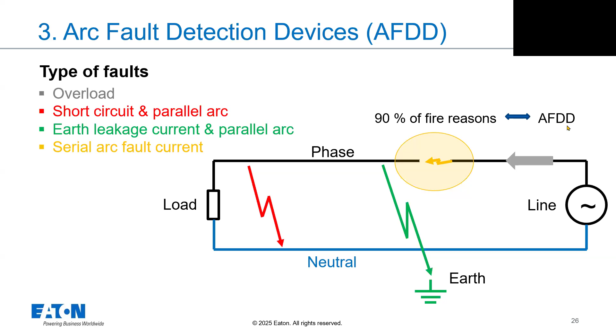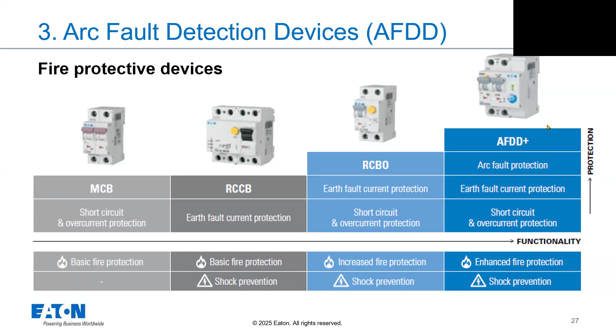I won't speak too much, graphically it's clear. If we compare protective measures like MCBs, there is only short circuit and basic overload protection, giving some basic protection against fire. With RCCB or RCBO, we get earth fault current protection as well. RCBO also includes an MCB inside, so we get short circuit protection too, but it's still not enough. For full protection, we need overload, short circuit, earth fault current, and arc fault protection together, either as one complete device or as separate devices. To achieve this level of fire protection, all three devices must be included.